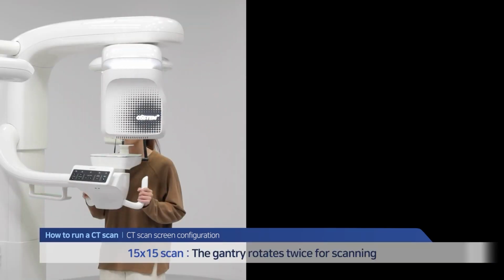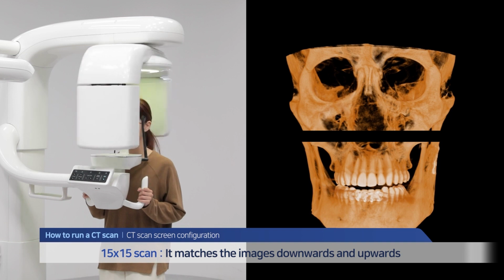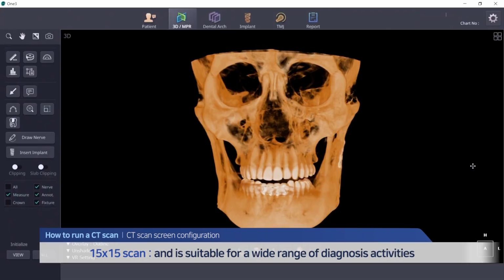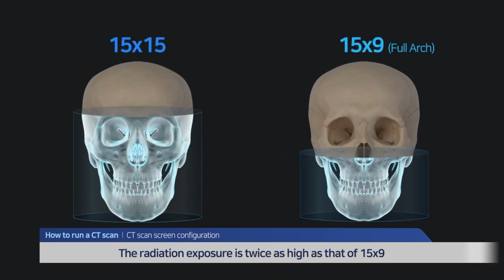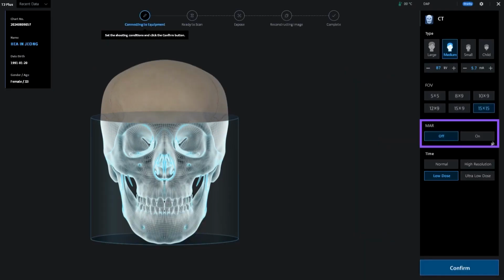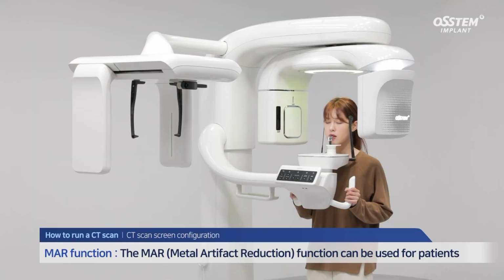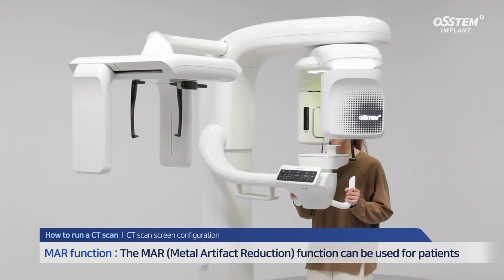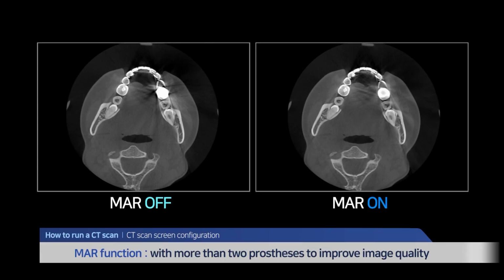The gantry rotates twice to scan from the lower jaw to the orbit, which is useful for a wide range of diagnosis activities. The radiation exposure is twice as high as that of 15x9. If the scanning patient has more than 2 prostheses, keep the MAR function on. This will reduce metal artifacts and facilitate diagnosis with a high-quality image.